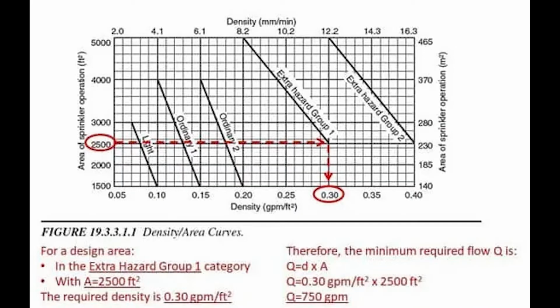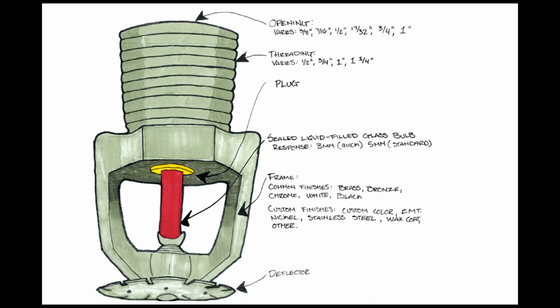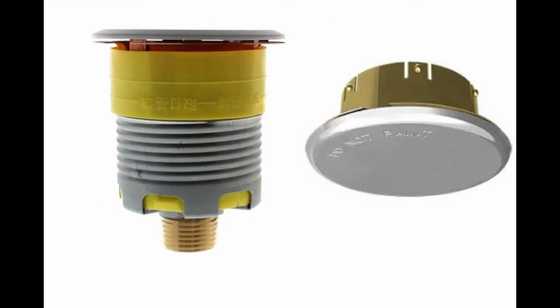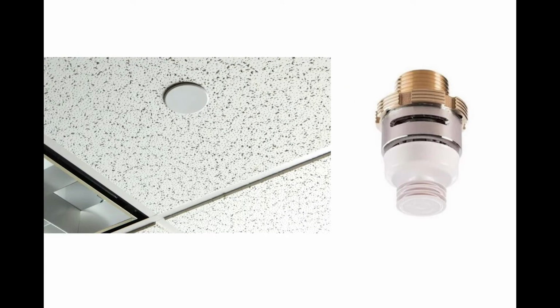Once the building occupancy has been established, the category it falls under will determine the sprinkler spacing and coverage area per sprinkler. In turn, this helps determine how many sprinklers are needed and what the required water flow pressure is. After using the formulas from NFPA 13 to calculate the required water pressure for each sprinkler, the next step in the process is to find the right sprinkler heads for the building. When choosing sprinkler heads, it is important to consider the max gallon per minute and the max pressure rating required of the sprinklers. The piping material, the sealing finish material, and the aesthetic properties of these sprinklers are considerations. In some situations, it might be important for the sprinkler heads to be concealed from view, in which case there are sprinkler heads with metal cover plates or white caps that function just as any other sprinkler head without being visible to the building occupants.